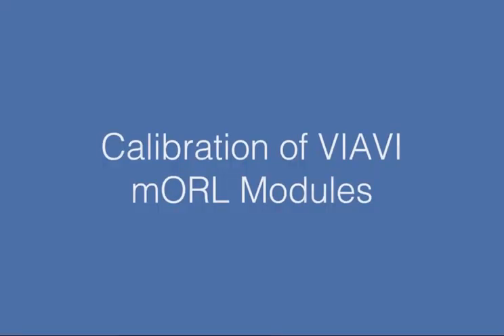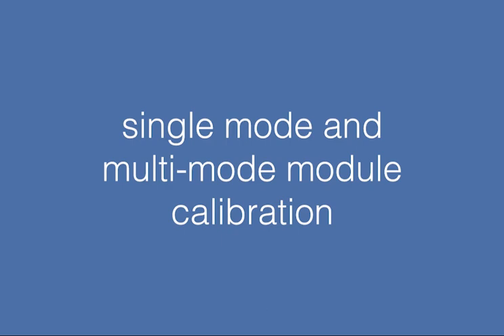This video shows how the VIAVI calibration kit and FOPLT software is used to calibrate VIAVI mORL modules. Module output power, return loss accuracy, as well as insertion loss and return loss linearity will be measured. Proper calibration assures measurements you and your customers make are valid.